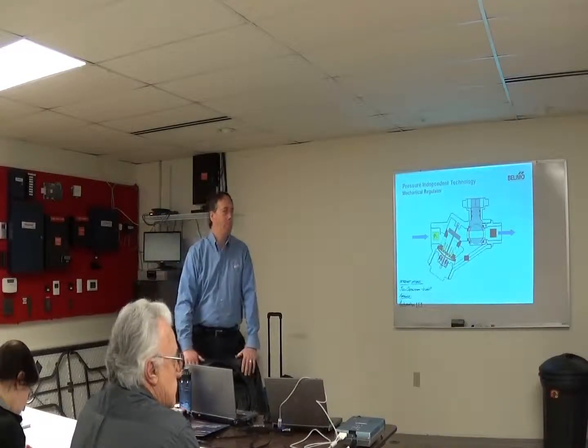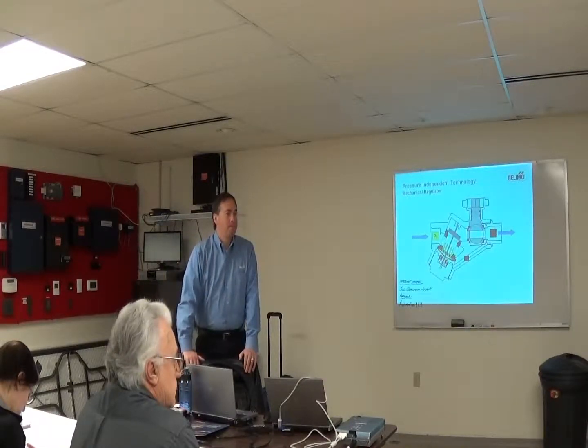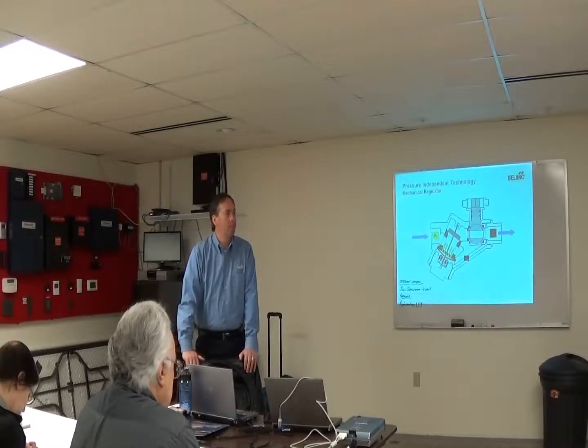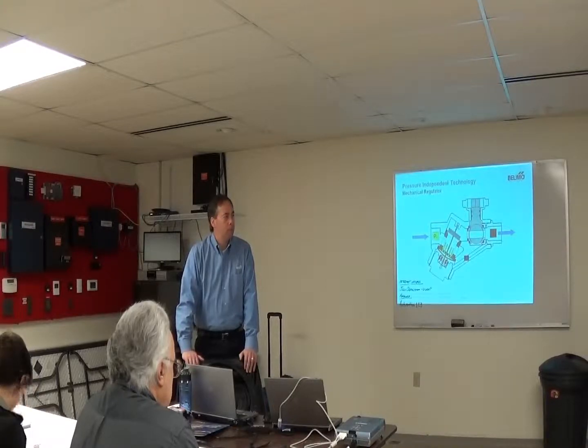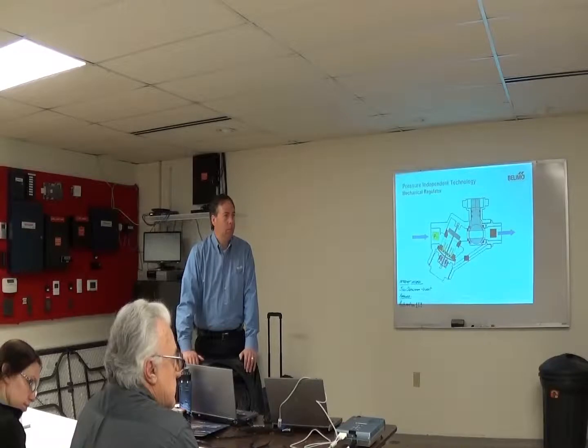Yeah, you can do BACnet MSTP or BACnet IP, but really all it needs is a 2 to 10 volt signal. You don't have to hook it up to anything special. The Delta T manager will work with just a 2 to 10 volt signal. But you can monitor it, you hook it back up. If you hook it up to BACnet, you get all those points. You can change whatever is capable of being changed.